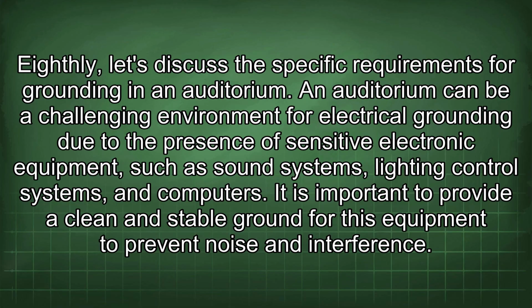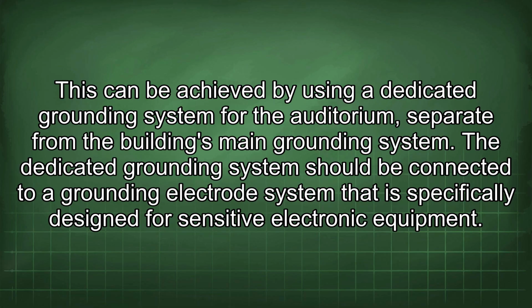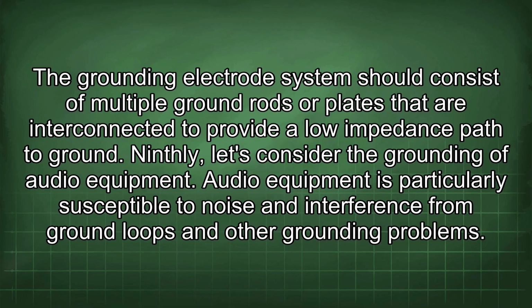It is important to provide a clean and stable ground for this equipment to prevent noise and interference. This can be achieved by using a dedicated grounding system for the auditorium, separate from the building's main grounding system. The dedicated grounding system should be connected to a grounding electrode system that is specifically designed for sensitive electronic equipment. The grounding electrode system should consist of multiple ground rods or plates that are interconnected to provide a low impedance path to ground. Ninthly, let's consider the grounding of audio equipment.